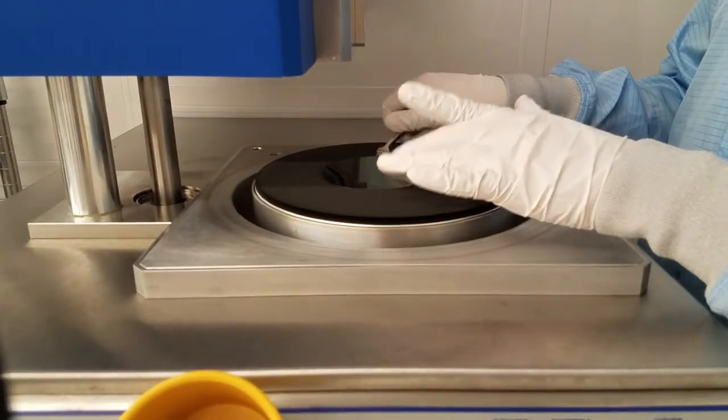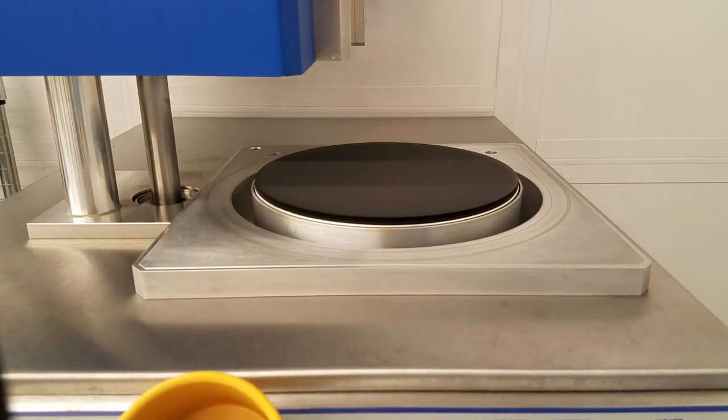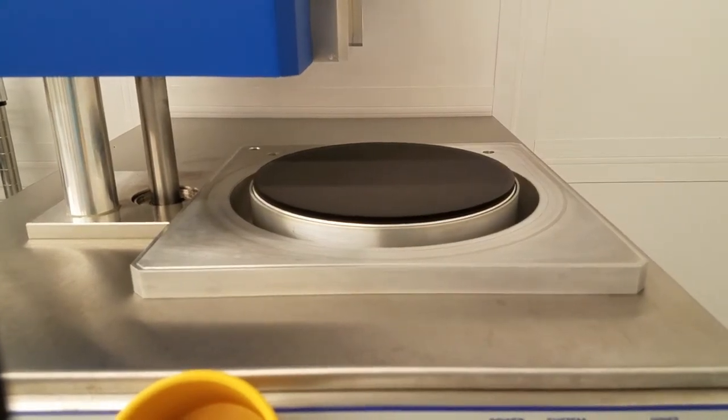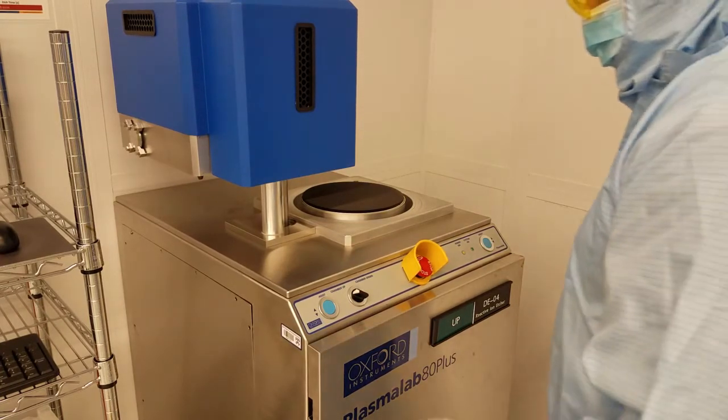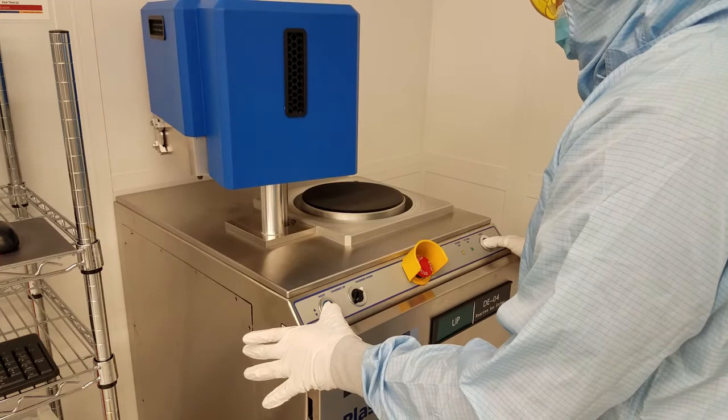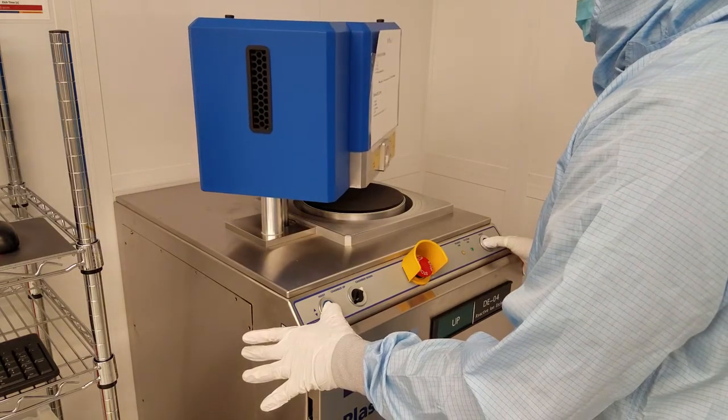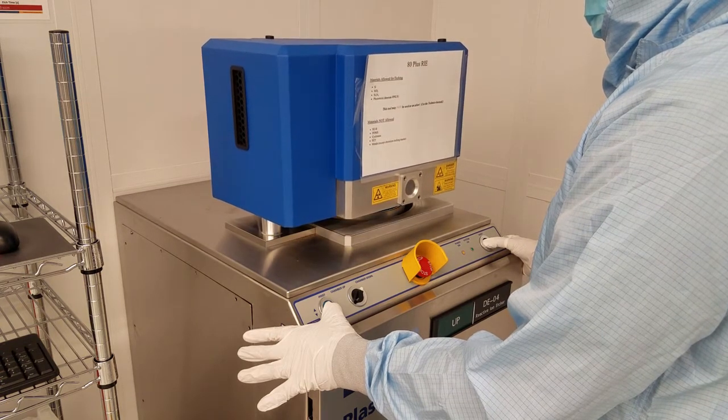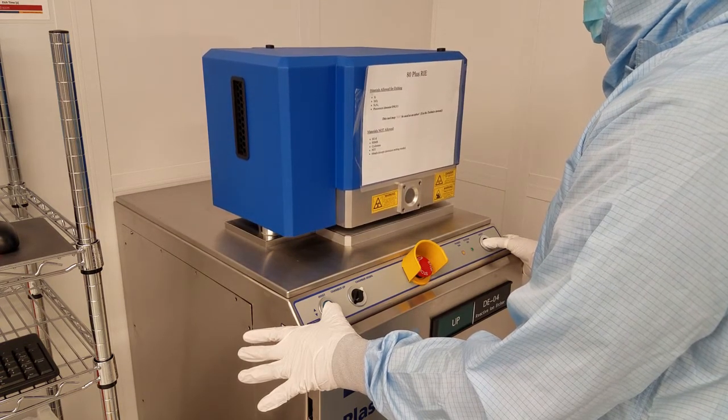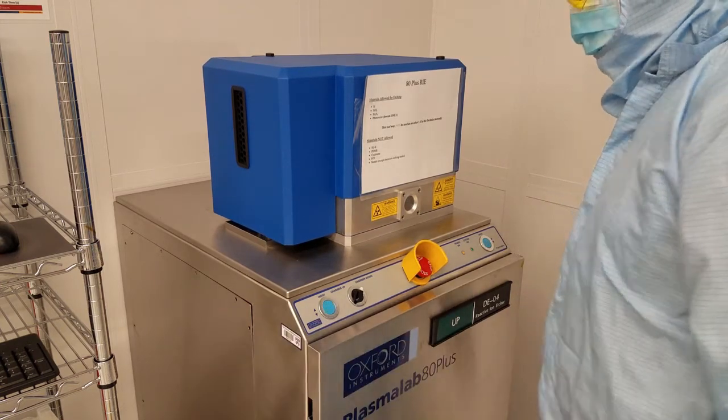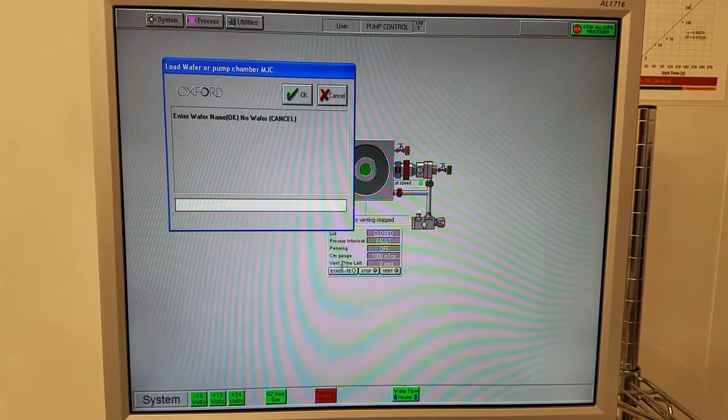You can run more samples now if you'd like, but if you're finished with your run, leave the chamber empty and we'll proceed to the chamber clean. Lower the chamber and evacuate the chamber. If you're going to run the chamber clean, click cancel. If you're going to run more samples, click OK.